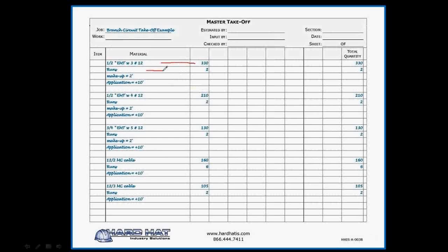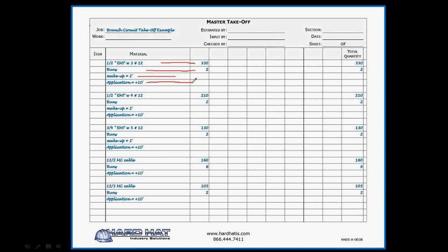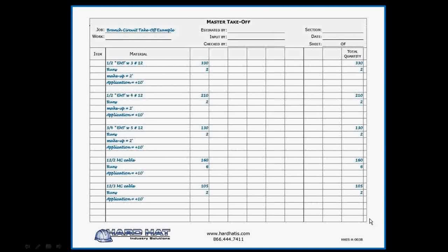I wrote it down, 330 feet of half-inch EMT with three number 12 wires. Again, notice on the left side under Material Column, it shows half-inch EMT with three number 12s. And to the right, 330 feet. Below that, I write the number of runs, which is 2. Next is the make-up length, which is 2 feet. Finally, the application, which is 10 feet. And then at the far right, I display the total quantity.